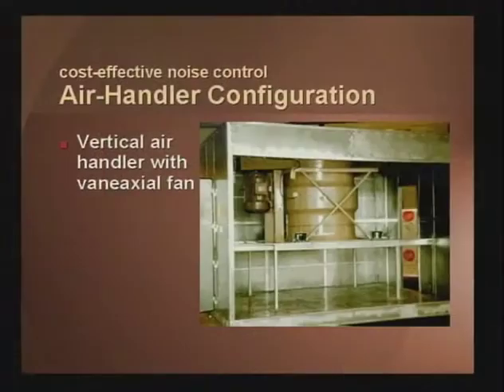In this picture here, we're showing one of the vertical configurations. The air comes through the inlet, which you're looking into, drops to the floor, is accelerated through the fan in a vertical plane, and is discharged into a discharge plenum above the unit. You can tap off that discharge plenum and go any direction you want to go. These units today are available typically in the 15,000 through 30,000 CFM range, and by putting two fans in parallel, twinning them, you can go from 30,000 up to 60,000 CFM floor-by-floor systems.